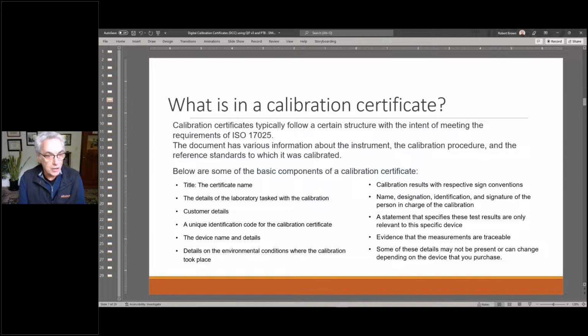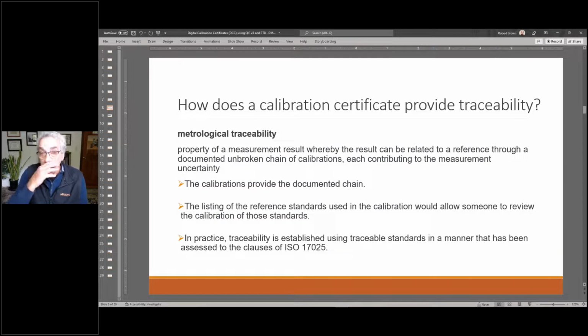Generally, calibration is done against a set of master standards that in turn may have a certificate from the National Institute of Standards and Technology in its certificate chain. So this is again the traceability. So metrology traceability is a property whereby the result can be related to a reference through a documented, unbroken chain of calibrations, each contributing to the measurement uncertainty. The calibrations are provided in this document chain.